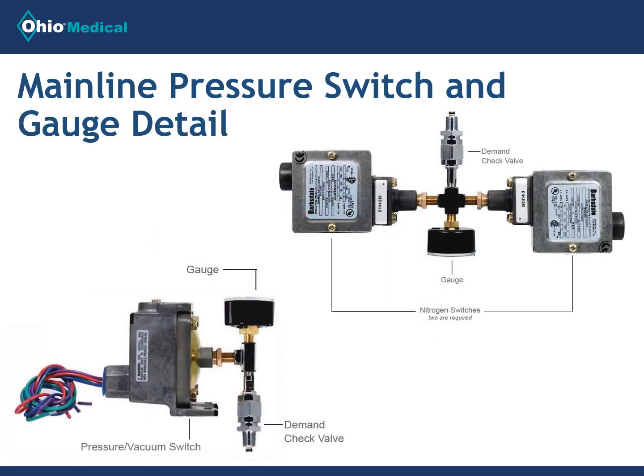Working in conjunction with our master alarms are pressure switch assemblies for both positive pressure gases as well as vacuum. Each assembly comes complete with the switch, gauge, and DISS fitting with demand check valve.